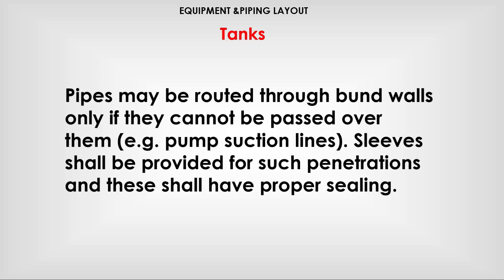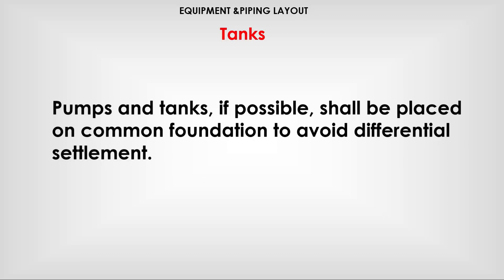Pipes may be routed through bund walls only if they cannot be passed over them — for example, pump suction lines. Sleeves shall be provided for such penetrations and these shall have proper sealing. Pumps and tanks, if possible, shall be placed on a common foundation to avoid differential settlement.